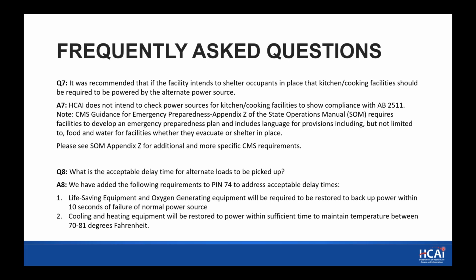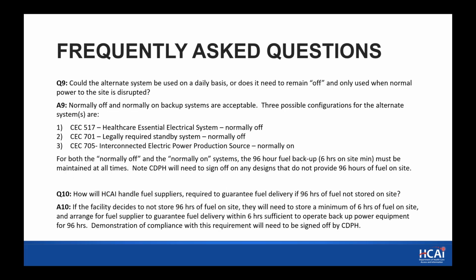Question 8. What is the acceptable delay time for alternate loads to be picked up? This was actually a really good question. I was really glad it was asked because we were able to put this into the PIN, and we've added the following requirements. Life-saving and oxygen generating equipment will be required to be restored within 10 seconds. And cooling and heating equipment will be required to restore power within sufficient time to maintain the safe temperatures that were identified in the PIN, between 71 and 81 degrees. Question 9.